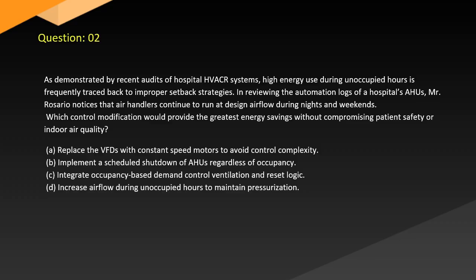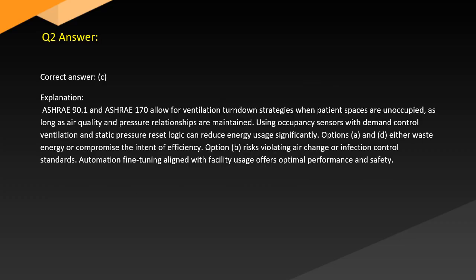A. Replace the VFDs with constant speed motors to avoid control complexity. B. Implement scheduled shutdown of AHUs regardless of occupancy. C. Integrate occupancy-based demand control ventilation and reset logic. D. Increase airflow during unoccupied hours to maintain pressurization. Answer. Correct answer. C. Explanation.